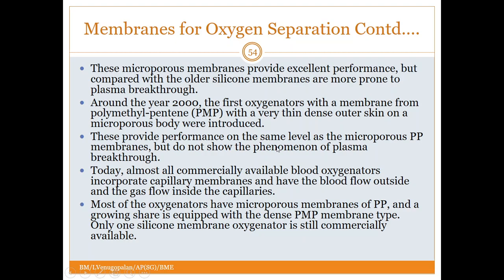But as of date, according to your textbook, there's only one silicone membrane oxygenator that is still commercially available. So silicone membranes have basically become outdated, and we are moving forwards towards microporous membranes of polypropylene and dense PMP membranes, right? So most of them are capillary membranes because they reduce the size and they do not cause much damage to the blood. And they're very efficient in interchange of gases.